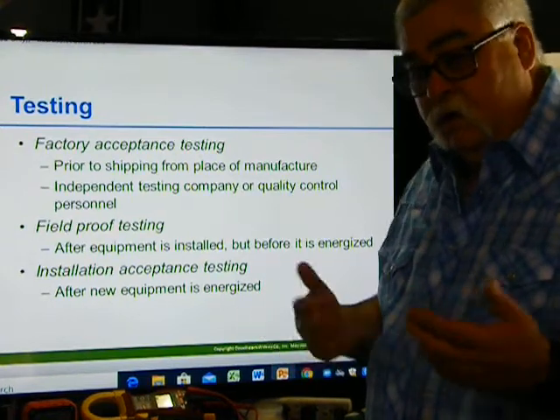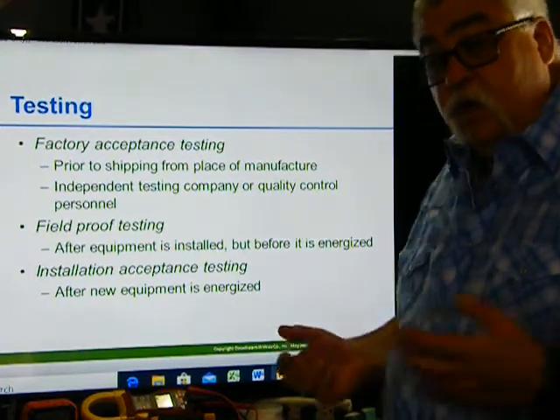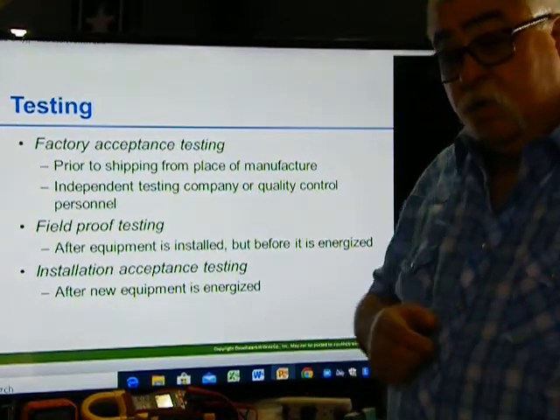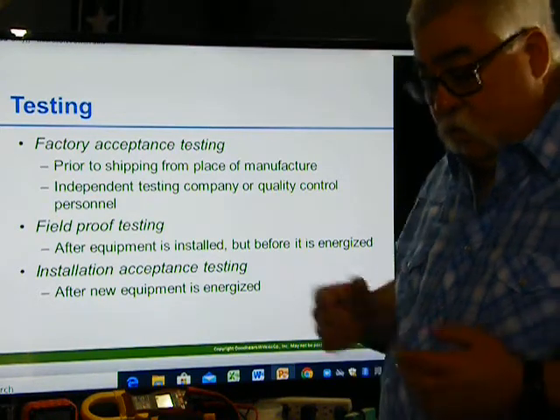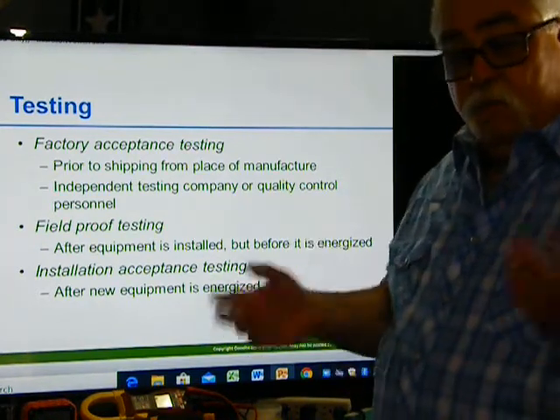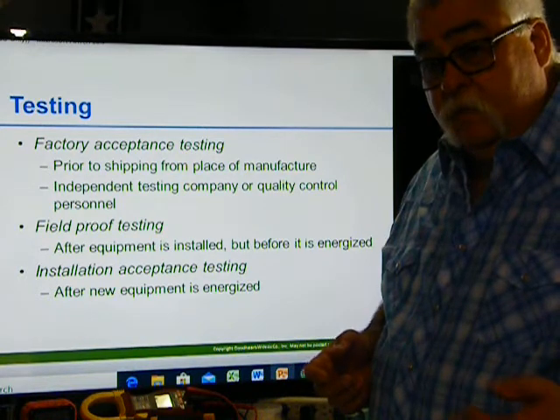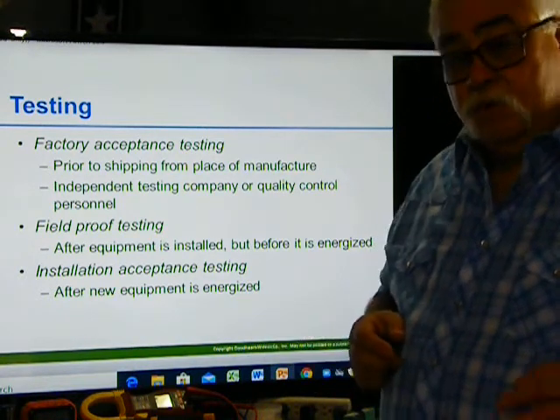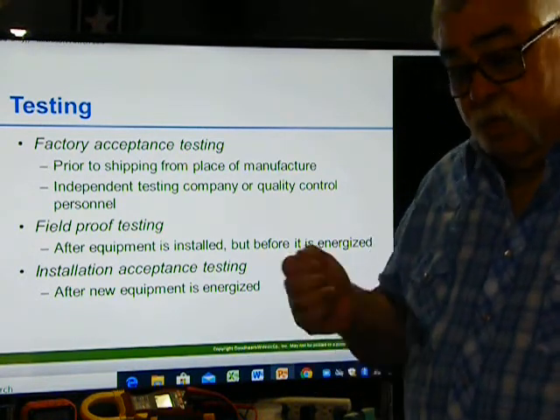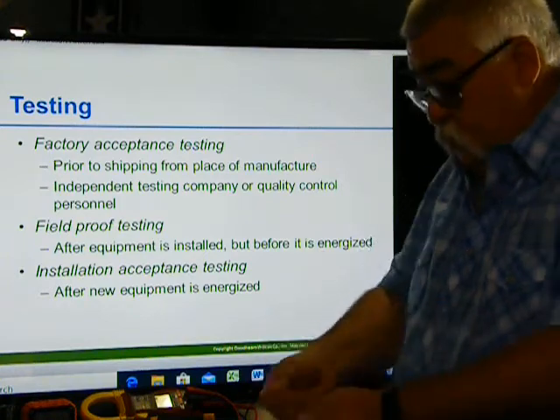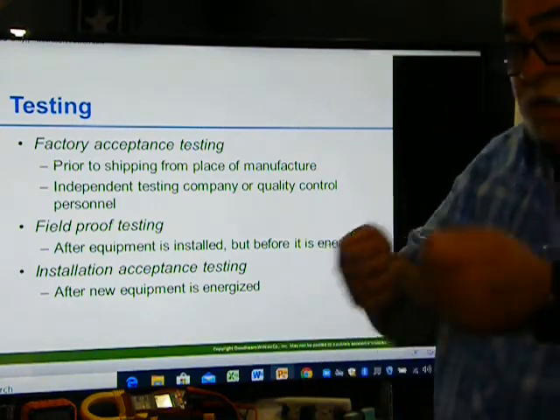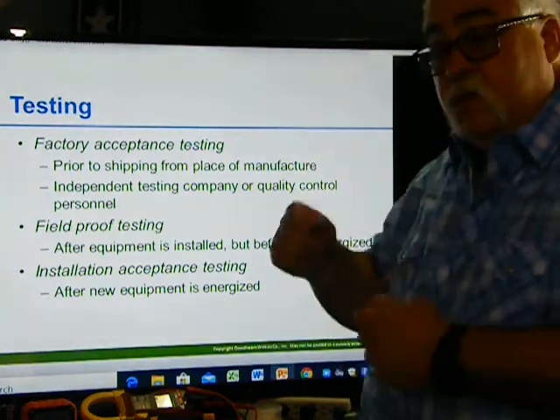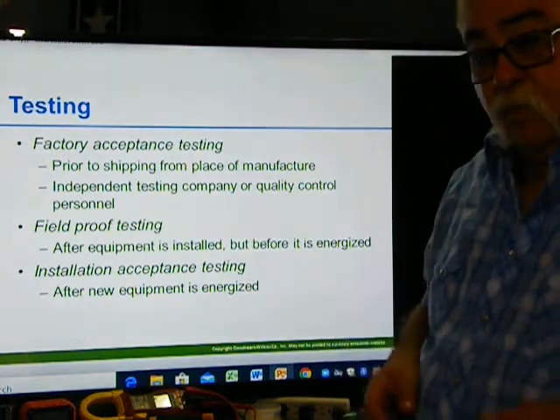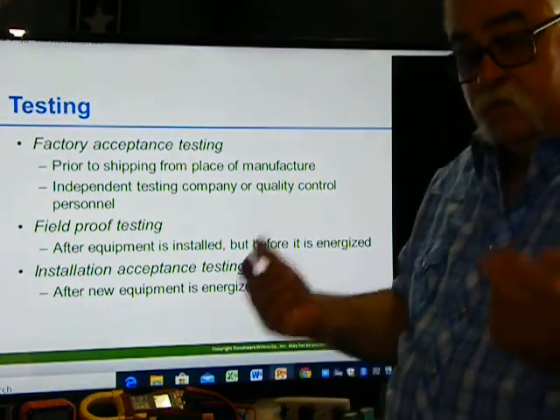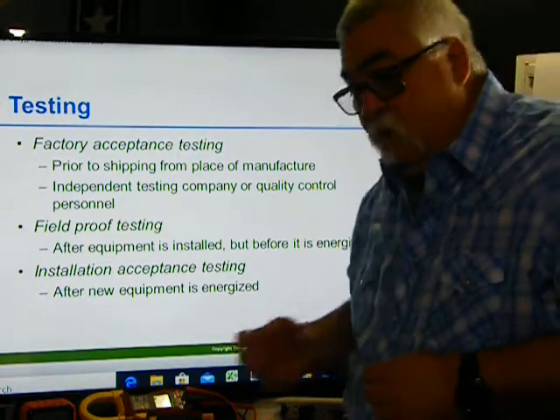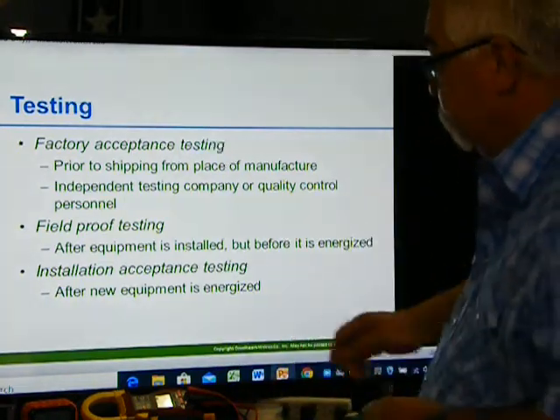I call it a dry run because they're looking at all the components to see that it's going to work the way it's supposed to. Okay, so they go in there and before they turn it on and work it, they check every component, make sure it's all tied in the way it's supposed to. They take ohm readings. I'm sitting there, I see them with a Fluke tester, and they're taking ohm readings, making sure that the ohm readings that they're getting are appropriate. No shorts, no faults, ground faults, or anything like that.